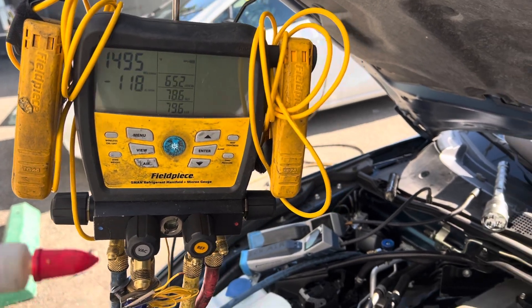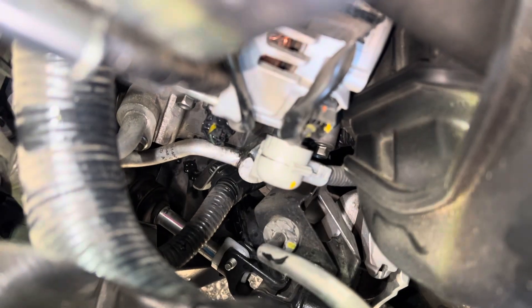Now let's take this one step further. Let's put a little Nylog down there and see if I can get my hands down there. We're going to see how deep we can get this vacuum — this is just experimentation to show you what Nylog does, if I can prove it. Let me get a little Nylog, goopity goop, down there. There we go — a little dab. Do you see that little shiny, slimy stuff right there?